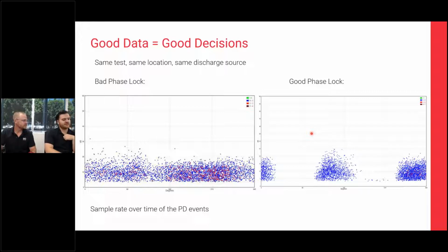Just had a question, just saying the graph numbers, do you want to explain decibels and the degrees? Okay, so we just had a question come through. On the left-hand, on the vertical axis, we've got the decibel level or the amplitude of whatever sensor you're using. So when we're doing a TEV recording, it will show you a decibel level from 0 all the way through to 60. If you're doing an ultrasonic, it'll be from -7 up to 70.